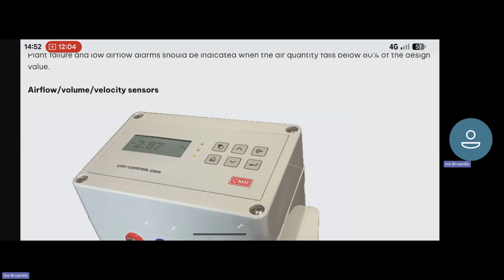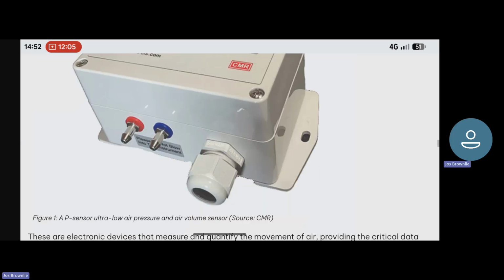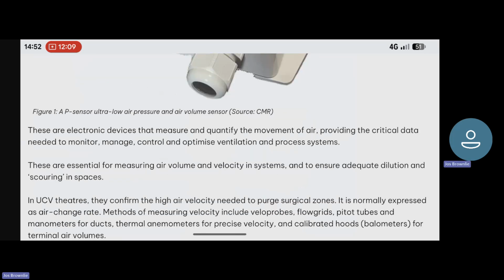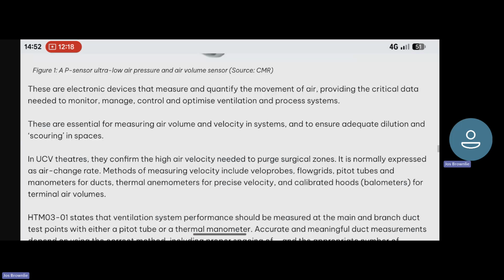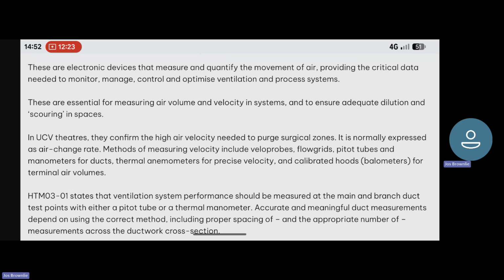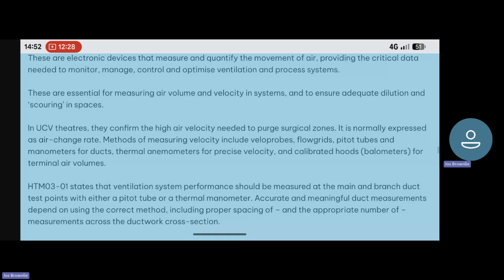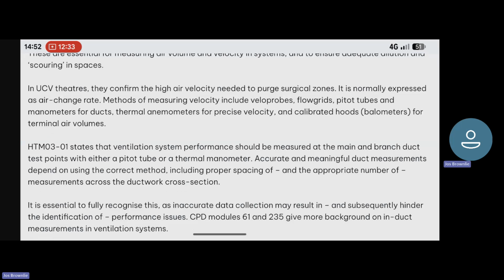Airflow, volume, and velocity sensors. These are electronic devices that measure and quantify the movement of air, providing the critical data needed to monitor, manage, control, and optimize ventilation and process systems. These are essential for measuring airflow, air volume, and velocity in systems, and to ensure adequate dilution and scouring in spaces. In UCV theatres, they confirm the high air velocity needed to purge surgical zones. It is normally expressed as air change rate.